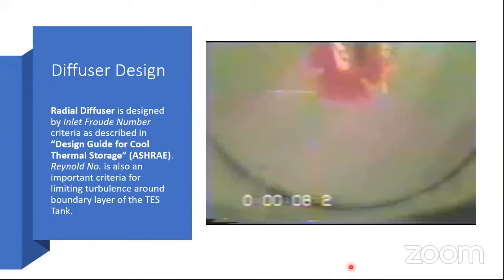Like I said earlier, the diffuser design is the heart of the system. As far as stratified tanks are concerned, if the diffuser is not correctly designed, the stratification will not happen, and there will be a lot of mixing that might take place, and the purpose will not be served. So the radial diffusers are designed by inlet Froude number criteria as described in the design guide for cool thermal energy storage. The inlet Froude number is an important criterion, and so is the Reynolds number, on the basis of which these diffusers are designed to limit the turbulence inside the thermal storage tank.